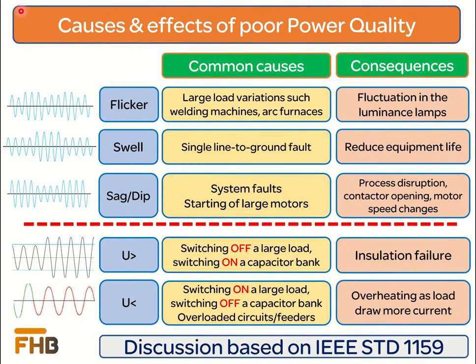Now we will discuss about the causes which create these short duration and long duration variations in the power system, and also the effects or consequences of these variations. Use of equipment such as large arc furnaces or welding machines produces fluctuation in the power supply. The effect of voltage flicker or voltage fluctuation is the variation in the light output which impairs our vision and causes general discomfort. Voltage swells are generally caused by faults in the power system. A single line-to-ground fault results in a temporary voltage rise in the unfaulted phases. Swells can also be caused due to switching off a large load or switching on a capacitor bank.